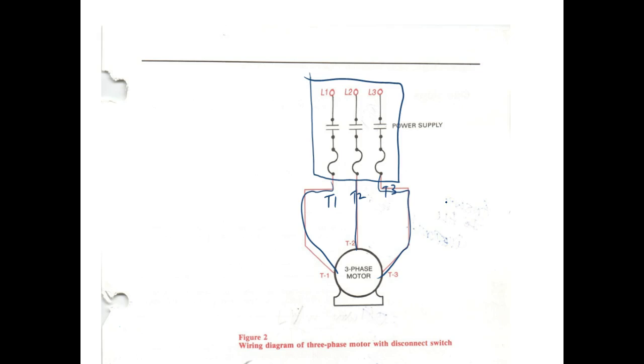So what you need to do is I'll come over there and ask which way the motor is supposed to run, because if you don't know which way it runs — and this happens all the time in this class, people aren't even paying attention to which way it's running — then they reverse it and don't know if it reversed, because they didn't know it was running in the first place. That's all we do on a three-phase motor. It's pretty simple to reverse a three-phase motor.